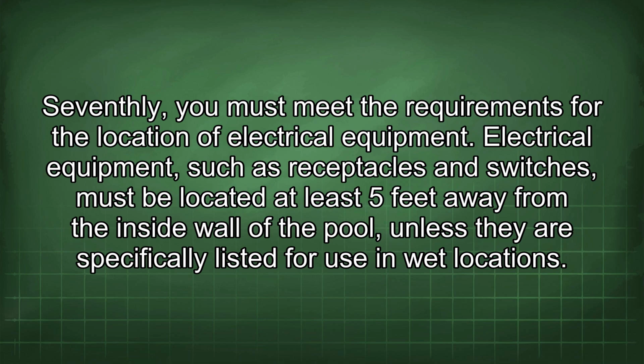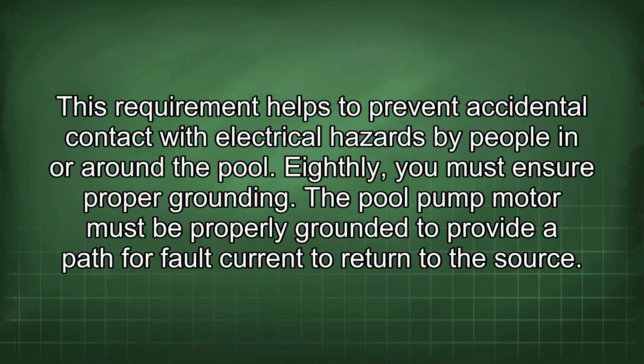Seventhly, you must meet the requirements for the location of electrical equipment. Electrical equipment such as receptacles and switches must be located at least 5 feet away from the inside wall of the pool, unless they are specifically listed for use in wet locations. This requirement helps to prevent accidental contact with electrical hazards by people in or around the pool.